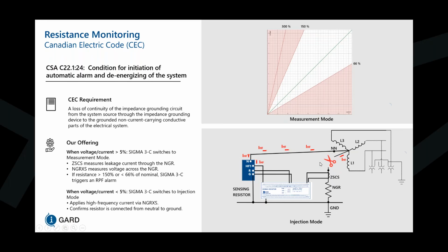So some of our competitors are using a DC-based injection. When their DC-based injection reaches the XO point, it sees the inductances as short circuits and leaks out into the system, finding this alternative path to ground. And because the DC resistance of these PTs is very low, it's going to see this alternative path and falsely confirm that it's checked the NGR when it has not.